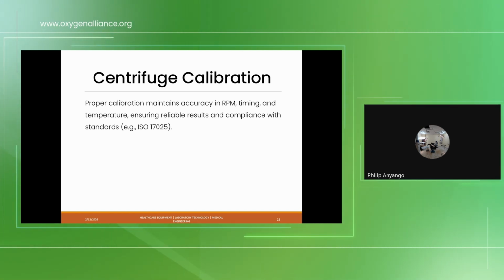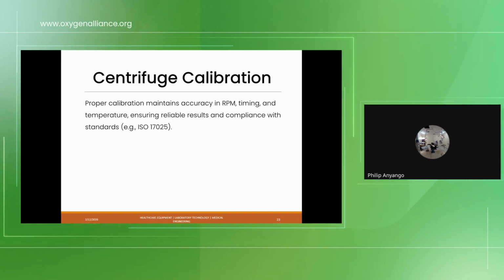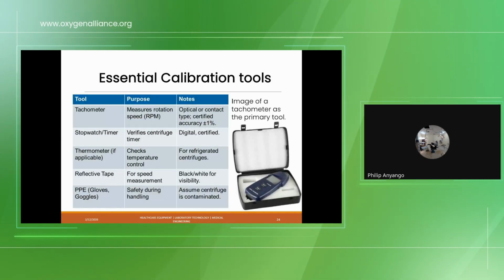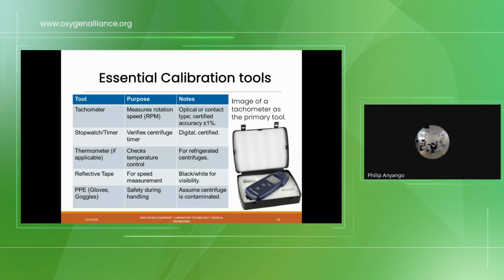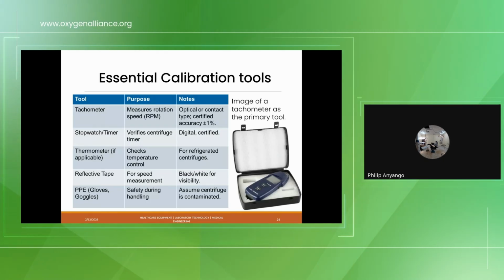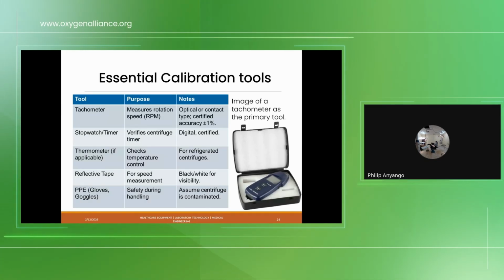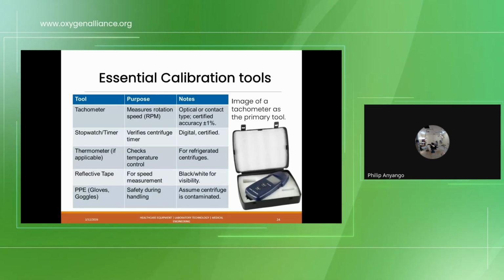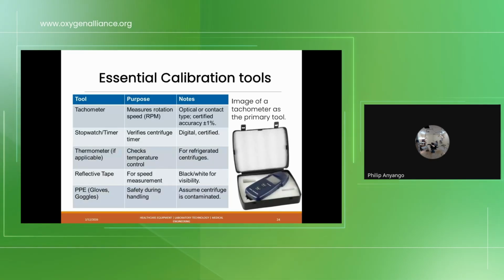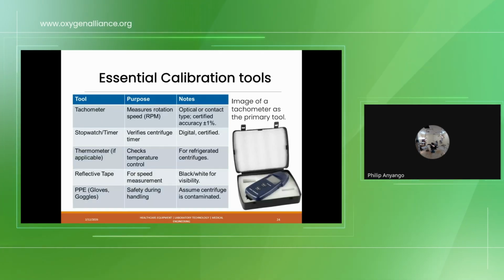I just wanted to make a comment on calibration. Yes, calibration is done after 1 year. A certificate is issued, but it is done by a third party. You cannot calibrate your own equipment. You can verify the speed of your equipment and make sure that it's running within range, but we call that verification. That's what you do after maintenance, after service, just to be sure. But calibration, you cannot calibrate your own equipment. It is a third party that does the calibration and issues a certificate so that you can have the confidence that your machine is working within the accepted parameters. Thank you.